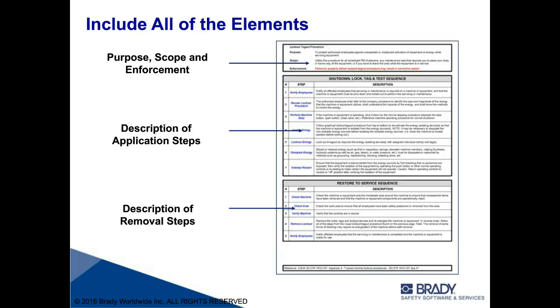As you move down, I'm getting ready to restore it to service. What are the descriptions of the removal steps? Again, with communication, test functions, make sure a machine is put back into manual and ensure that it isn't going to automatically start up as soon as an energy source is turned on or engaged.